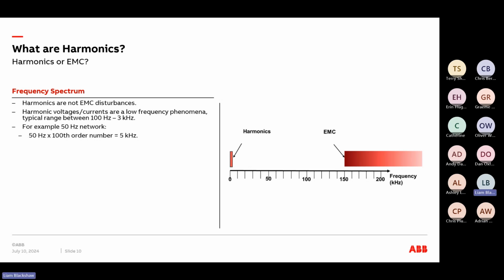But yeah, typically harmonics are at low frequencies. There can be frequencies above maybe the 5 kilohertz threshold. But often people, and this is the key misconception, a lot of users are trying to reduce harmonics by using methods that decrease RFI disturbances. But of course, because these frequencies are different, these methods do not address harmonics. And typically harmonics is more of a conductive phenomenon, while RFI disturbances can be both conductive and radiative as well.